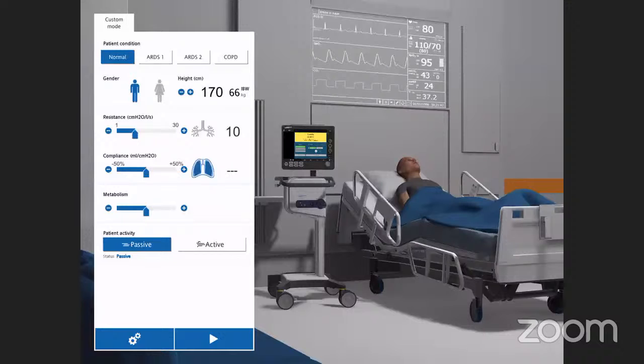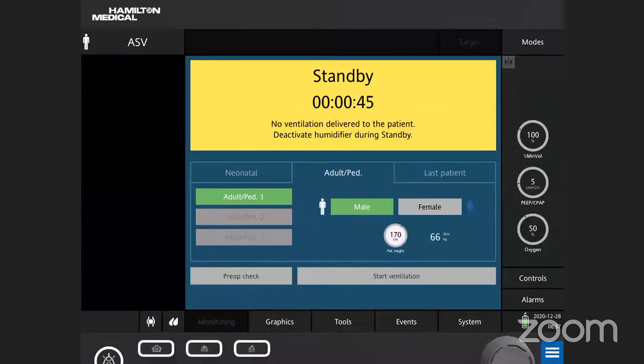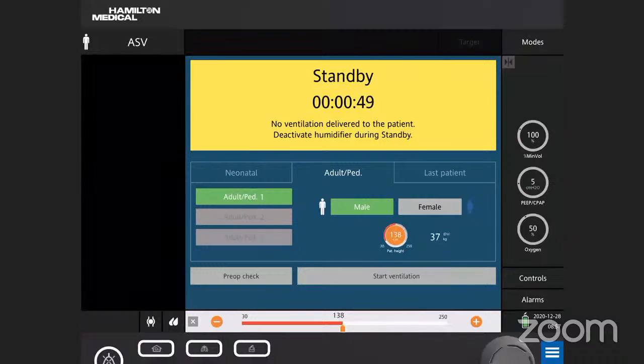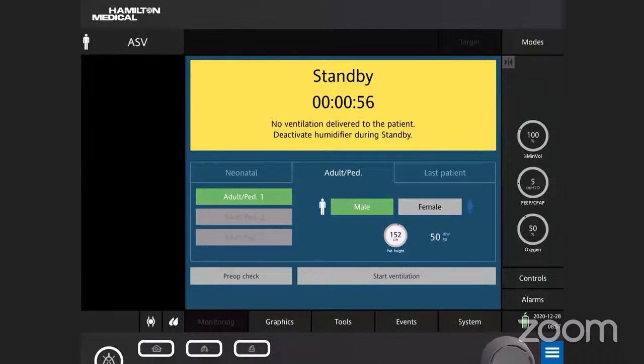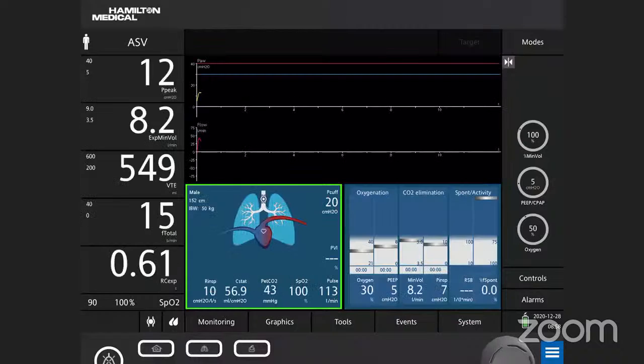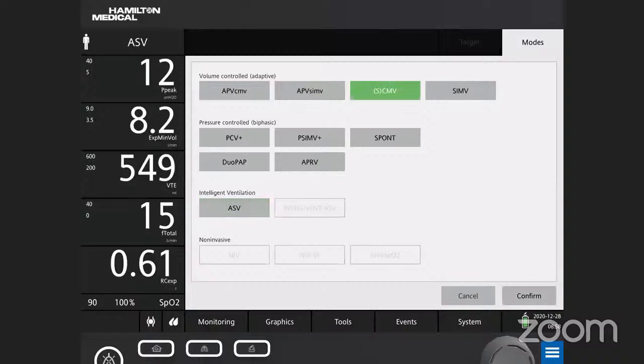So what you can see here is that the patient's gender you have to enter into the ventilator. The height of the patient has to be entered, and whether the patient is active or passive. So we will do a passive one. So this is the ventilator, and you can see that this is a male patient. We can keep around 152 centimeters height. And so the ideal body weight or the predicted body weight as per the formula, the ventilator itself is giving you, so it is only 50 kilograms. This patient would be around 80 kilograms, but once you enter the height of the patient, you will get a predicted body weight. So you will be ventilating the patient only as per the predicted body weight. So now you have to go to the, you can start ventilation. You can go to the mode. So we will do a controlled mechanical ventilation first.